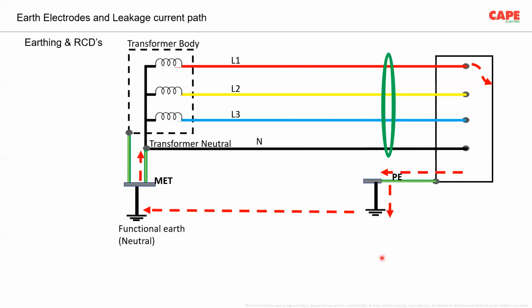What does the residual current device do? It is measuring the current in a junction. It is measuring the current of all the live conductors, all the current carrying conductors. Whenever there is a leakage of current, actually the current is escaping from this circuit. It is escaping from this junction. This particular device measures the current which is escaping from the junction, say for example 30 milliampere, and it trips.